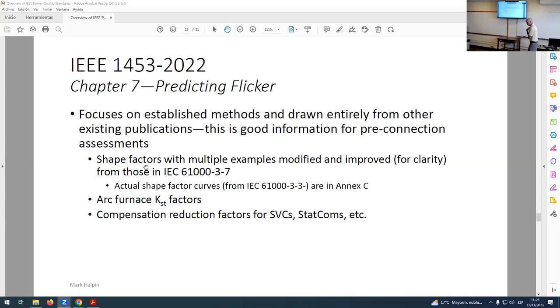We have, and certainly in Alabama and the U.S. in general, we have quite a few arc furnaces. They're major sources of flicker. There are simplified ways to predict the Pst flicker production or effect of an arc furnace. It's called a KST factor. All right? For sure, almost for us in Alabama, any new furnace customer, by default, they have to come with compensation. Right? Well, different compensation technologies have known different effects as far as their mitigation effectiveness, okay? So-called reduction factors. The U.S. community didn't know anything about any of that. And so in 1453, we tried to put that kind of practical application-oriented material, okay?